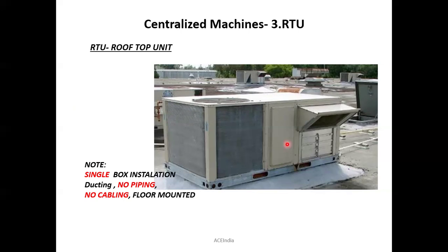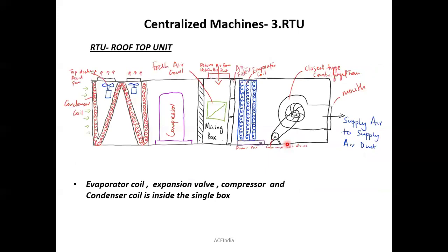Now let's discuss the components right inside this rooftop unit. We can see this is a typical arrangement of an RTU. So the concept is very simple, guys. One side should be connected with the compressor and condenser, that's it. And the other side should consist of the expansion valve, evaporator, and blower fans. Then the middle portion is termed the mixing box or a side portion, whatever you can call it. But in this picture, it is mentioned in the middle, isn't it?